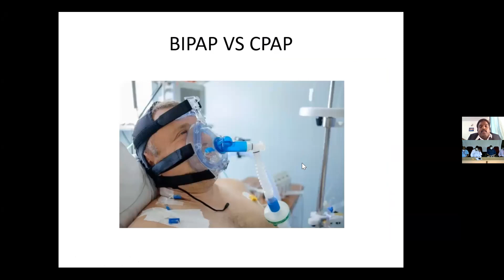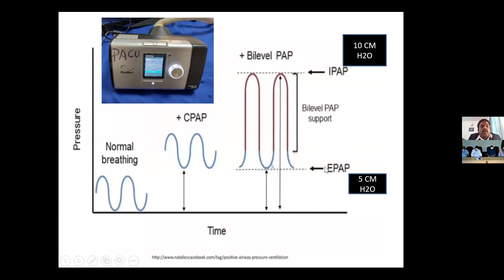Next come some mechanical supports for the lung, a BiPAP or a CPAP. You see the patient with normal breathing on a CPAP. In CPAP, you give some amount of positive end expiratory pressure in a spontaneously breathing patient. This is the CPAP. What is BiPAP is that there are two sets of pressures. One is the low pressure, that is EPAP, during expiration, and during inspiration it is IPAP. The inspiratory pressure should be kept around 10 centimeters, and the expiratory pressure is almost like PEEP, it is 5 centimeters of water. This is a BiPAP machine that we use. So you already know how we give CPAP, a constant pressure during both inspiration and expiration.